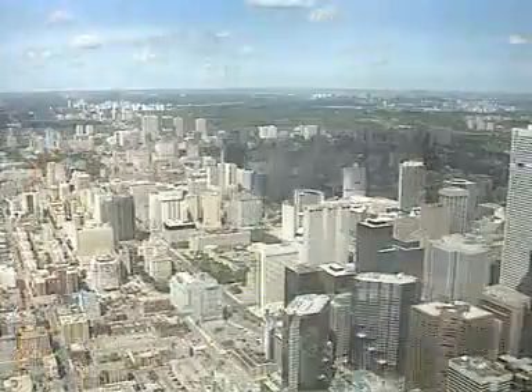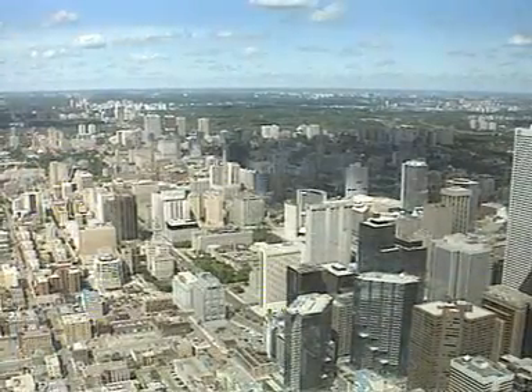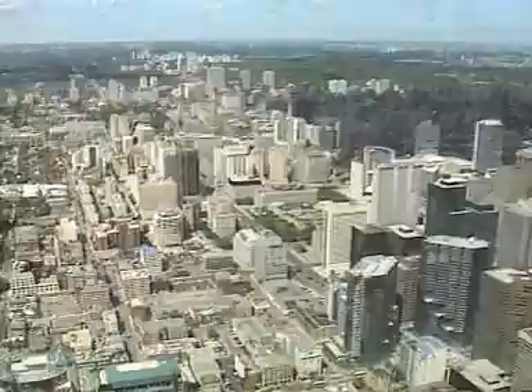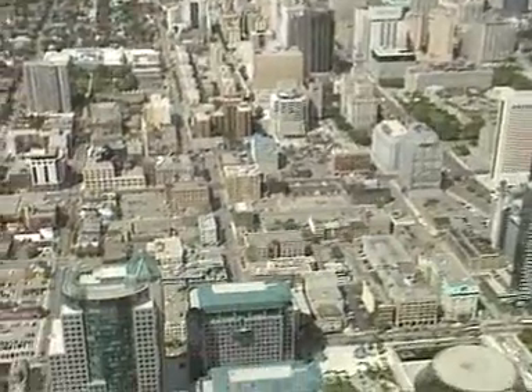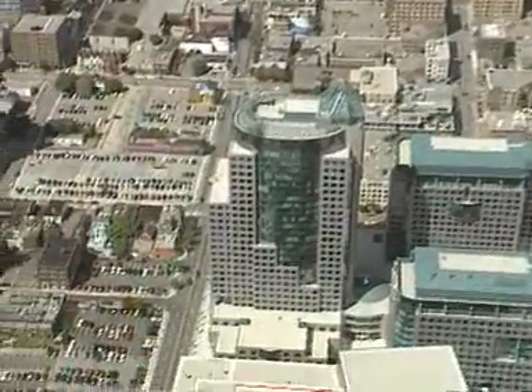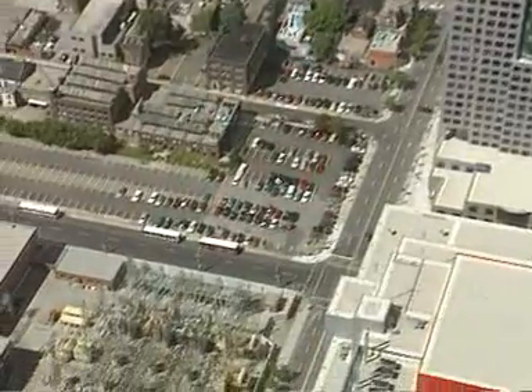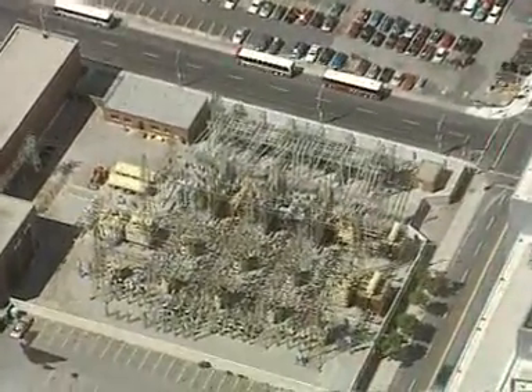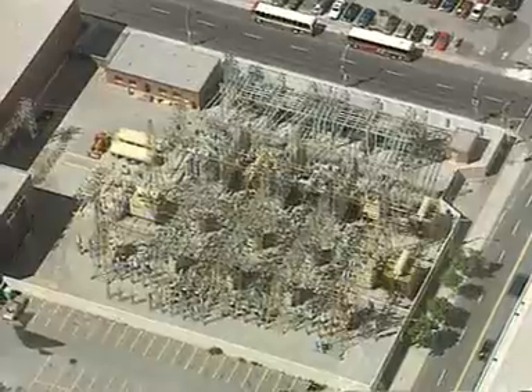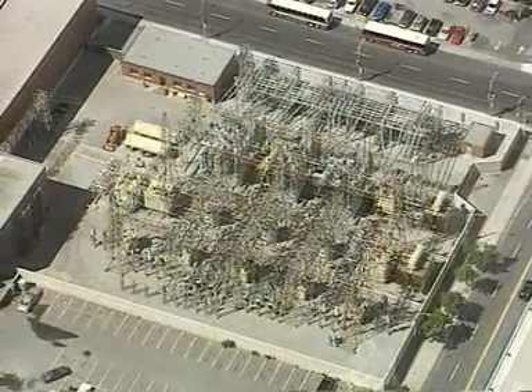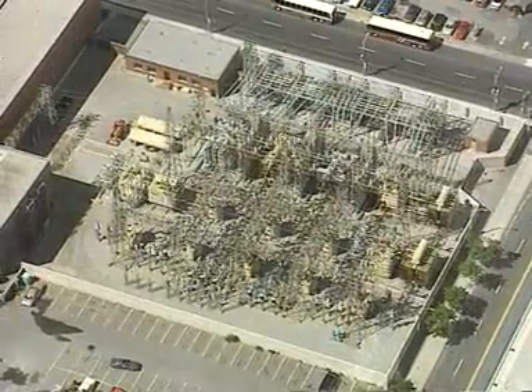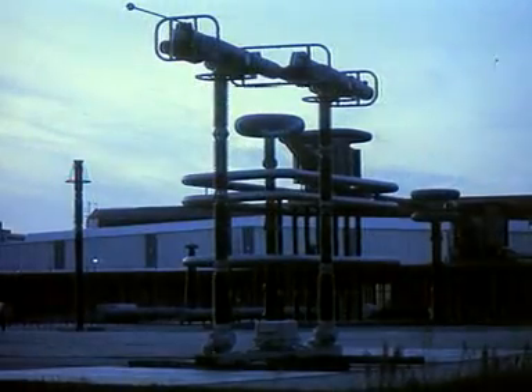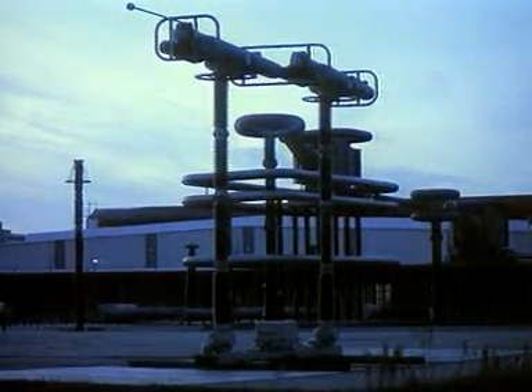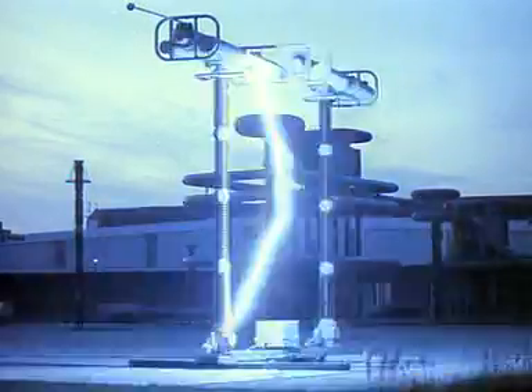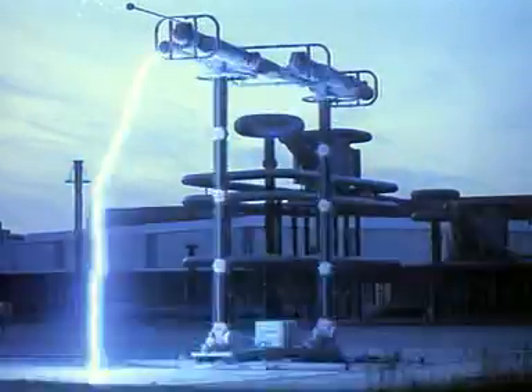Power demand continues to grow in conurbations. Top performance, high-voltage switchgear in the load centers takes care of reliable transmission and distribution of the required energy. But nowadays, there is no space for such air-insulated substations in densely populated areas. Their size is determined by the limited insulation capacity of air. This calls for substantial clearances between live parts.